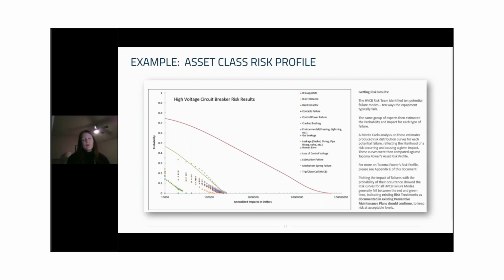For high voltage breakers, we worked with our subject matter experts to identify the list of failure modes you see there on the right, to understand the ways our breakers might fail to perform as expected. We then worked with those experts and our own data to assess risk for each mode, resulting in those risk distribution curves you see color-coded by failure mode on the graph. We can see that the distribution curve showing the risk for the majority of the failure modes just barely cross over that green line in almost all cases, indicating that the maintenance and capital replacement processes we have in place for high voltage circuit breakers as a whole are keeping us at an acceptable level of risk.